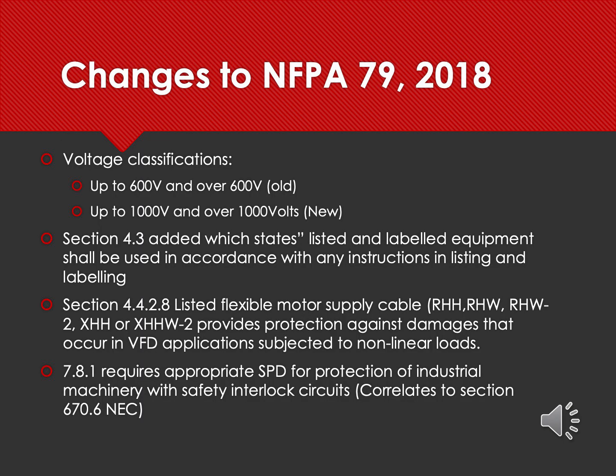Let's take a look at the changes to the NFPA 79 2018 edition. First and foremost, code harmonization drives consistency between NFPA 79 and UL 508A. The new revision of NFPA 79 is updated to be consistent with the current UL 508A voltage classification tables, which define up to 1000 volts and over 1000 volts, from the previously defined 600 volt classifications. So in the 2018 edition of NFPA 79, all the voltage classifications are called out in the 1000 volt nominal voltage range. The next one is Section 4.3, which was added to NFPA 79 and states that listed and labeled equipment shall be used in accordance with the manufacturer's recommended guidelines.